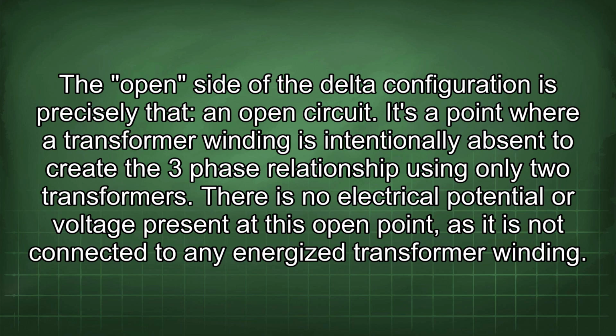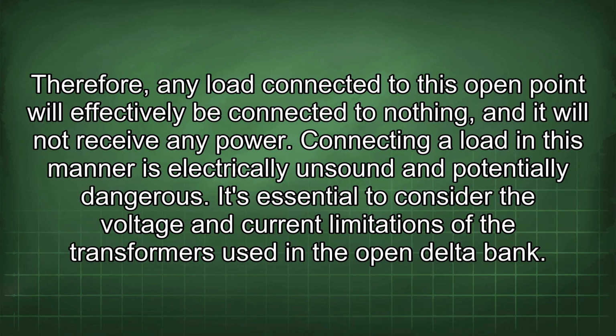There is no electrical potential or voltage present at this open point, as it is not connected to any energized transformer winding. Therefore, any load connected to this open point will effectively be connected to nothing, and it will not receive any power. Connecting a load in this manner is electrically unsound and potentially dangerous.